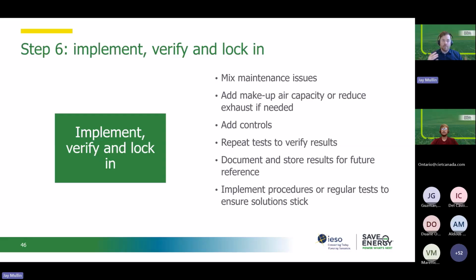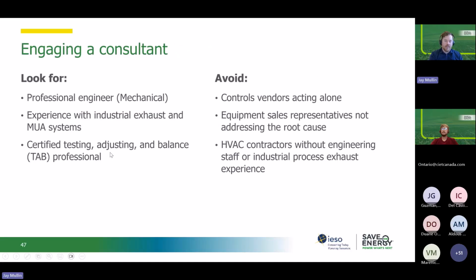So whether that's BAS alarms or checks or regular maintenance checklists, preventative maintenance on some of those critical systems for it, making sure that all of these things that are being implemented to make sure your pressure is balanced are staying in place and that they aren't falling behind again. Some tips on engaging a consultant, things to look for: engaging consultants that are professional engineers, mechanical engineers, especially if you think makeup units are undersized or missing, or if safety issues are involved, because they're better positioned to evaluate code compliance, modify systems, stamp drawings if needed.